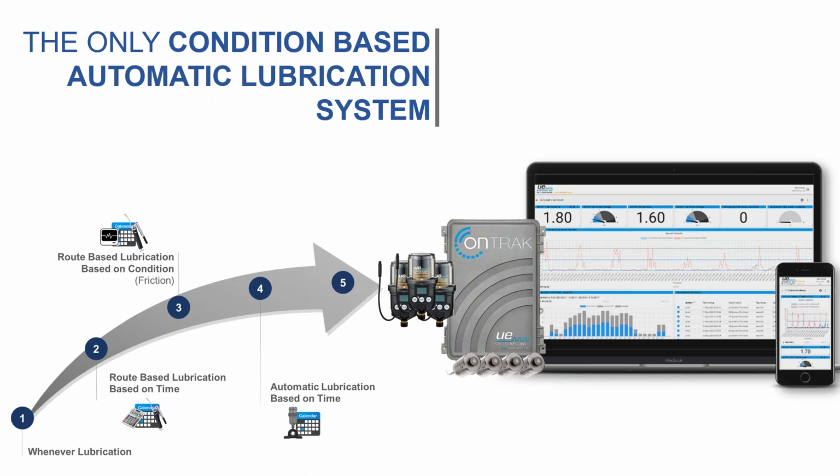And they fundamentally solved an issue. They solved the issue of making sure you use the right grease, given you put the right cartridge in it, and it's contaminant free. If you install it right, there's no way for dust and stuff to get in, at least through the grease port. Now, if you have a busted seal or things like that, stuff can still get in. So 3 and 4 really came out at the same time. What we had from a grease caddy product is really good at determining the when and how much, and the single point lubricators are really good at making sure it's the right grease and it's contaminant free.